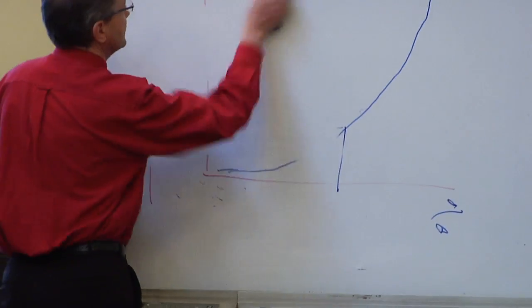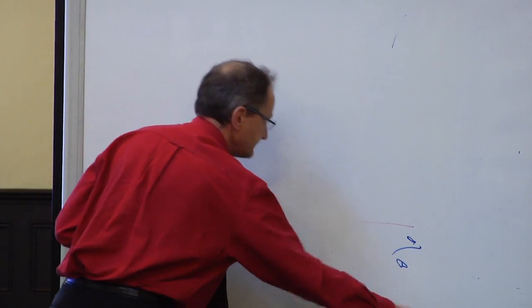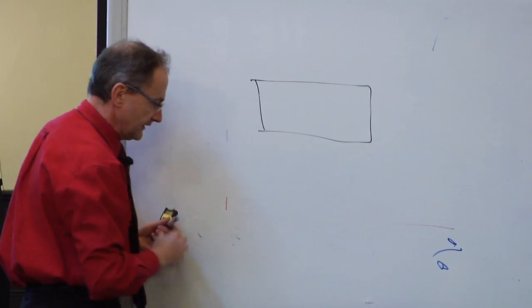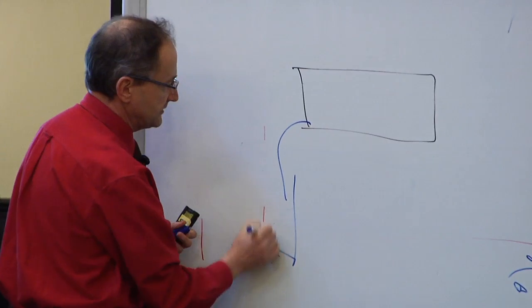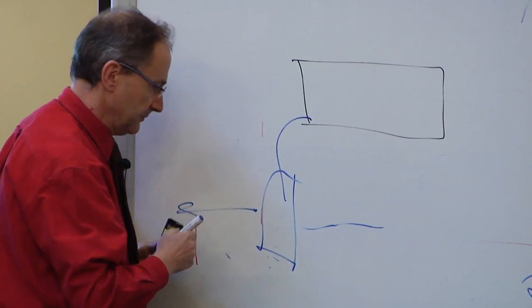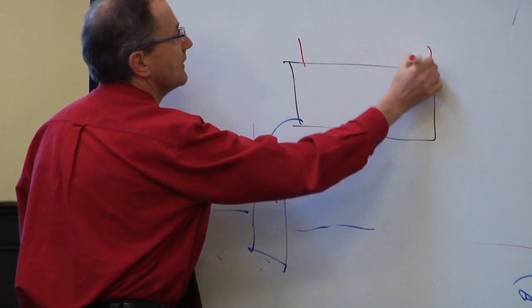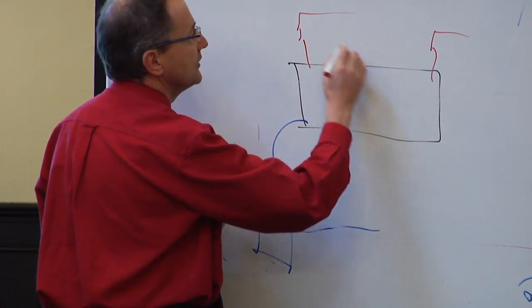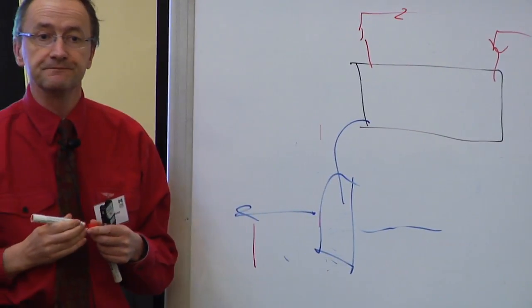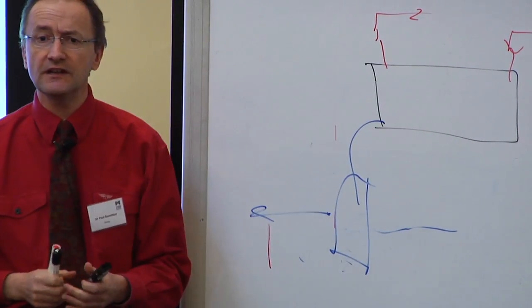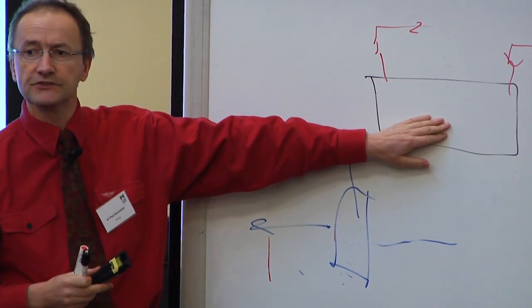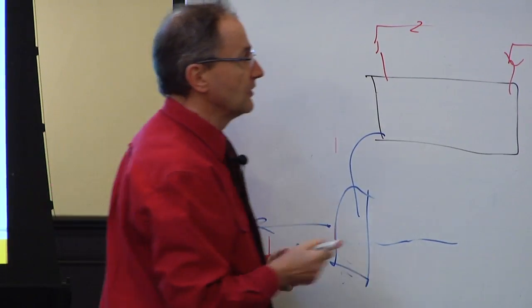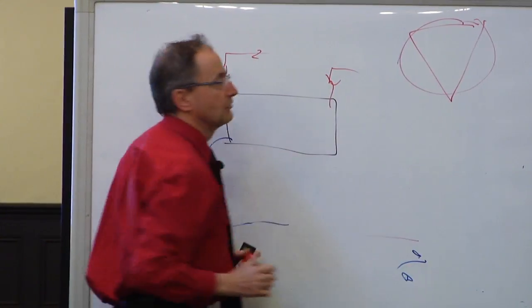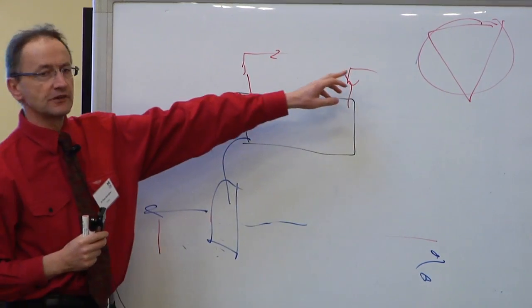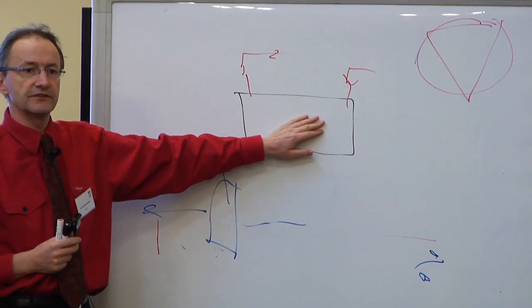What do I mean by that? Well, if we've got a water-cooled package unit, a little bit like a chiller, it's got a cold bit, which has typically got air going through it, and it's got a hot bit, which rejects heat, and that goes off to a cooling tower. So this has got water running through to cool the package unit down. Now, the way these systems are generally set up, that water runs irrespective of what this unit is doing. So we end up at the top of the building with a chonking great pump running continuously, most of the time circulating water through package units that don't need any water.